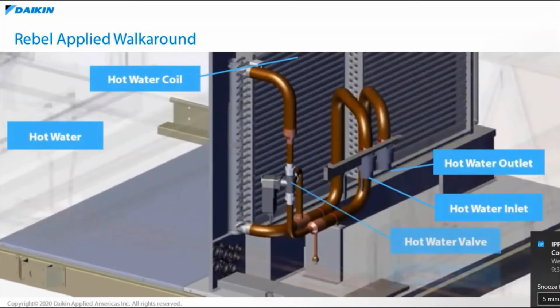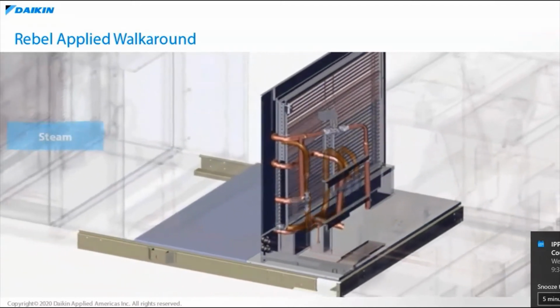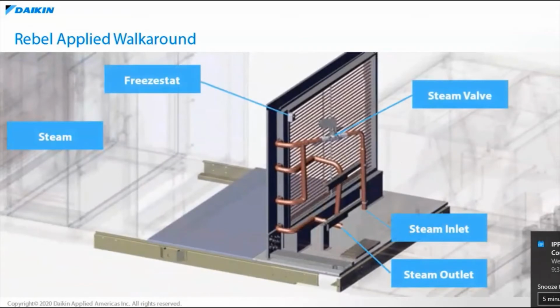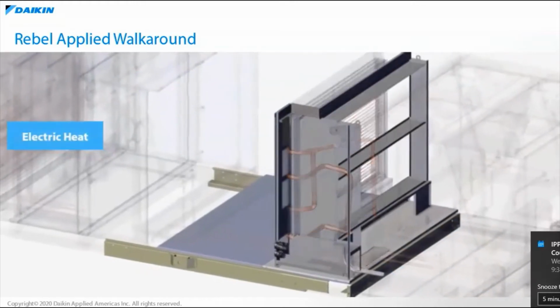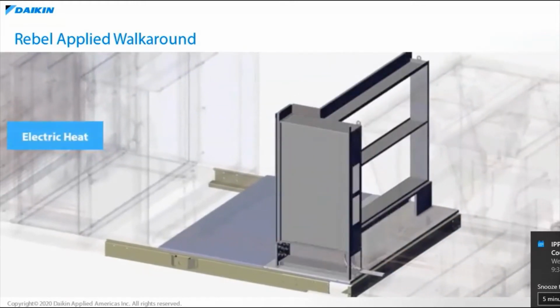Hot water heating is also a heat option, and if so equipped, includes the hot water coil, inlet and outlet valves, and a hot water drain connection. A factory-provided hot water 2- or 3-way control valve is available. Another heating option is a steam coil. Steam coils will be furnished with inlet and outlet connections and optional freezestat. The last heating option is electric heat. Several types of electric heat control are available. The heater banks will be located in this area.